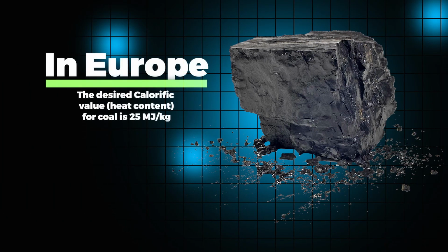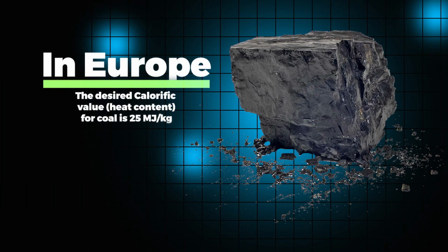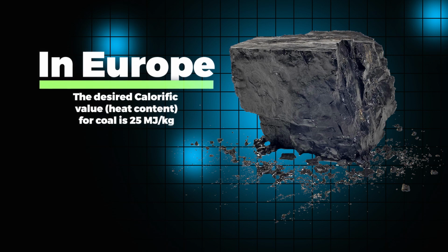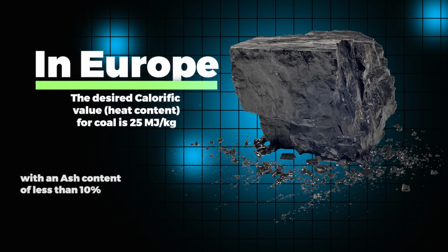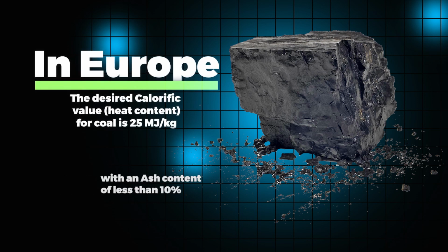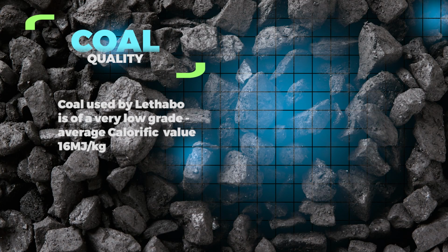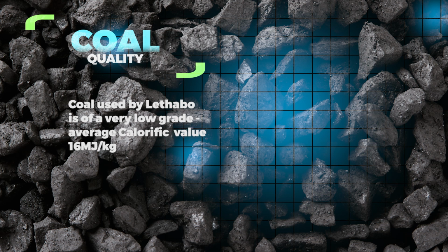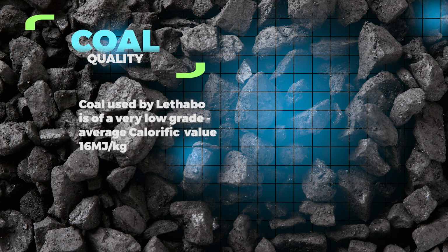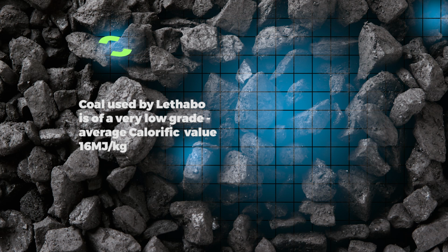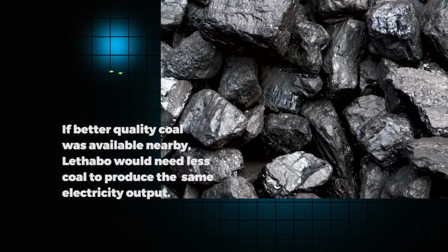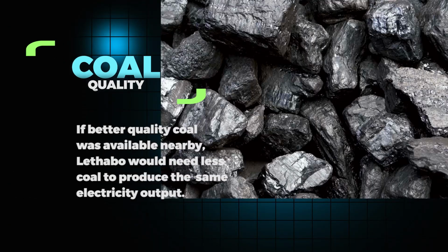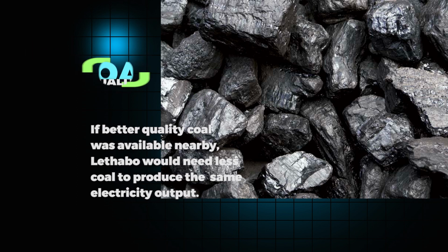In Europe, the desired calorific value or heat content for coal is 25 megajoules per kilogram, with an ash content of less than 10%. The coal used by Lethabo is of a very low grade, with an average calorific value of 16 megajoules per kilogram and an ash content of 42%, but has the advantage of containing less sulfur than other coal types. If better quality coal was available nearby, the power station would need less coal to produce the same electricity output.